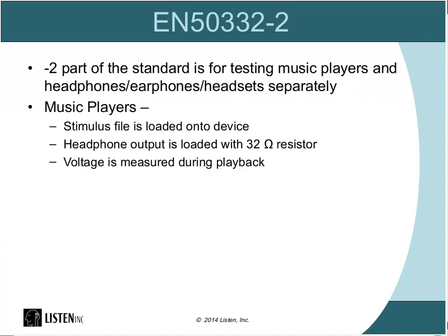In the Dash 2 part of the standard, we now test the devices separately. So if all you do is make headphones, then you'd be interested in the Dash 2 part of the standard here. Or if you are making a smartphone and you need to test it by itself, then the Dash 2 part of the standard is for you. So here we're going to be measuring them separately. And so we have a few different sequences that will make up this part of the test.